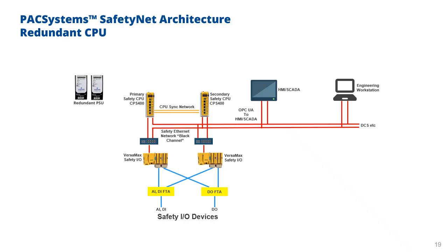This is more what I expect to see as a standard solution. Now we have 2 safety CPUs with a primary CPU and a backup secondary CPU, synchronized using that LAN 3 with a dual Ethernet network. This time we've also got dual networks down to the I/O and dual networks to the OPCUA communications to HMI SCADA and to the DCS. Note, because we've got dual networks now, we now exceed the capabilities of what the Versamax safety bus interface can achieve. So now we do need those switches. So this is more what I would expect to see as a typical architecture. And this one also gives us the capability of having more I/O, which I'll come on to in the next slide.